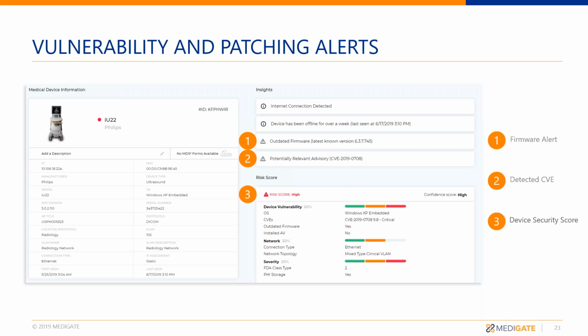Finally, the FDA class type. This is a class 2 device, so it is on the higher side. There is going to be patient impact if it gets compromised. And it is also known for transmitting and storing PHI. So 50% of that device vulnerability led to a high, 20% of the severity led to a high, and the 30% was a medium. So 70 out of 100 was a high, so the overall risk score is a high.